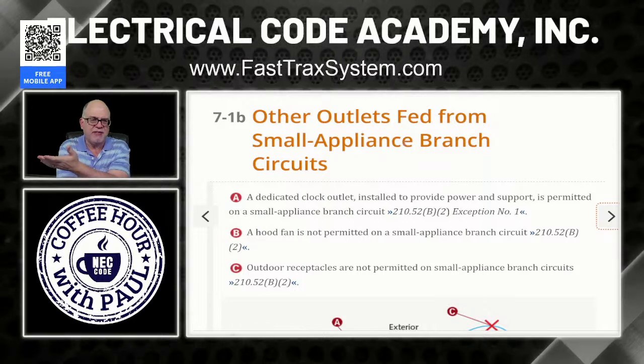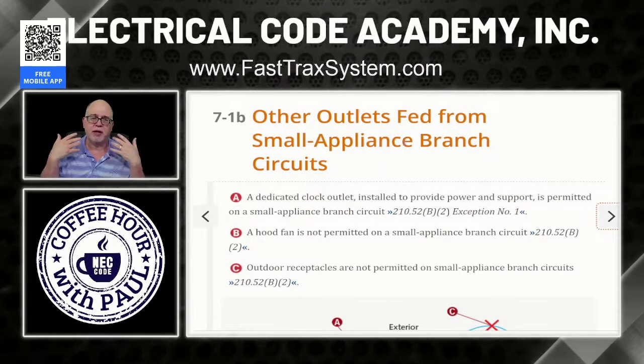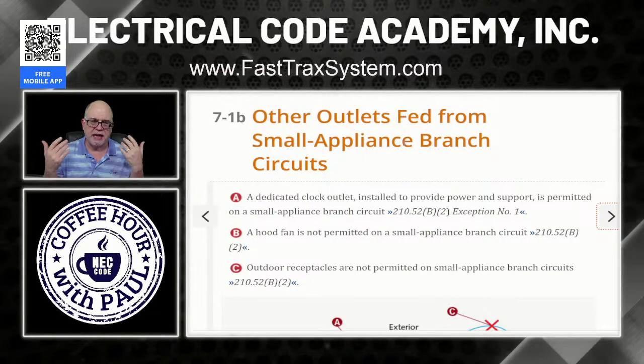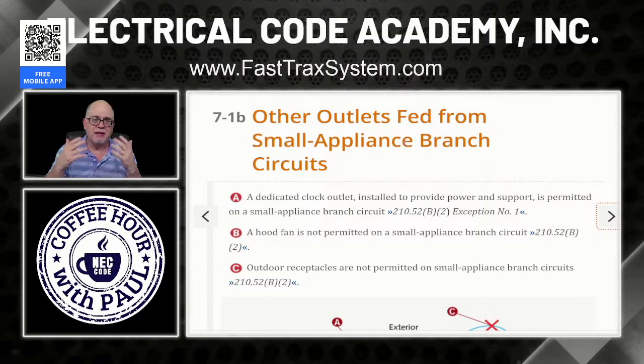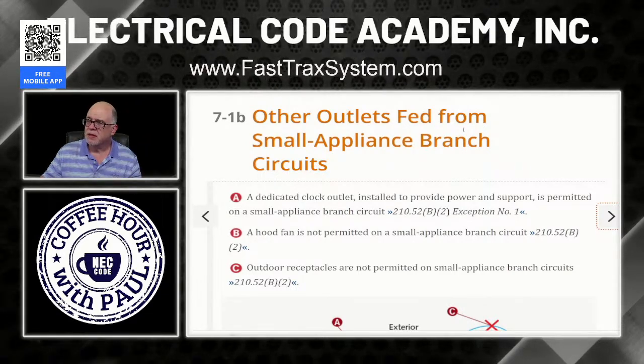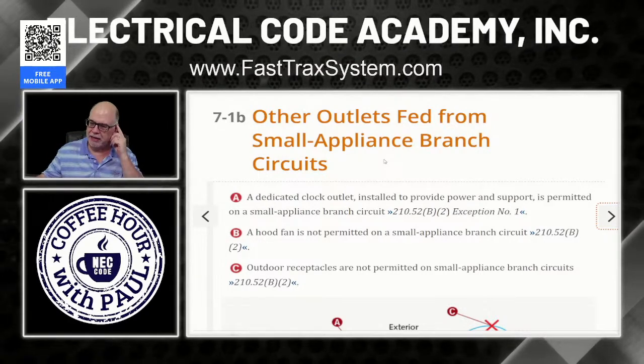Okay, we know how to space it now. 2 foot, 4 foot rule. We know that that same small appliance branch circuit has to also pick up the other receptacles that are in the actual kitchen, pantry, dining room. And can we have more than two? Absolutely. So we could have two that stay in the kitchen and the third one picks up the dining room or the pantry. That's fine. Not a problem. But you have to have at least two. But let's talk about what else can actually be on that small appliance branch circuit.